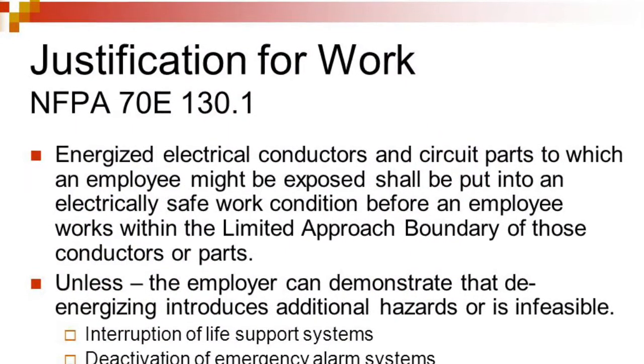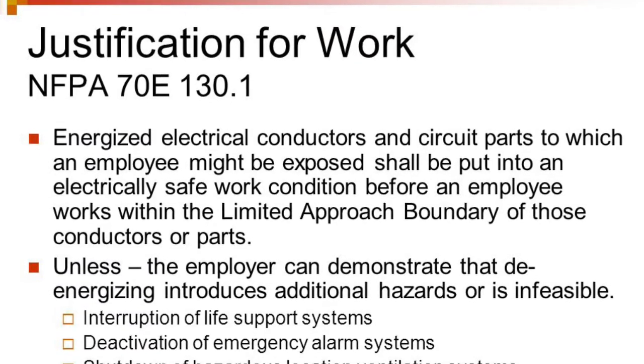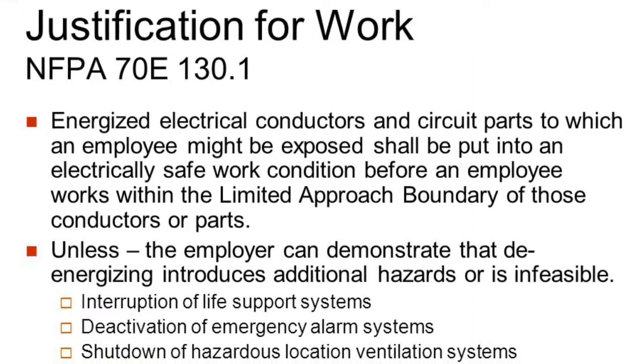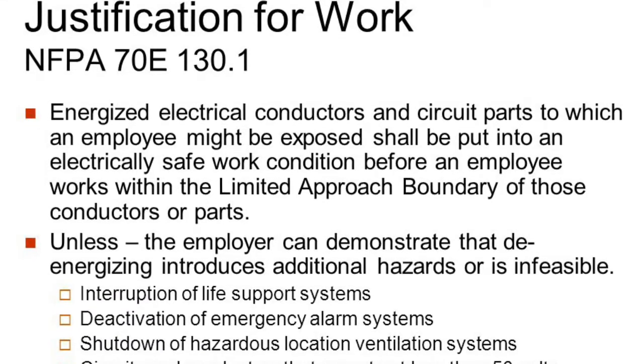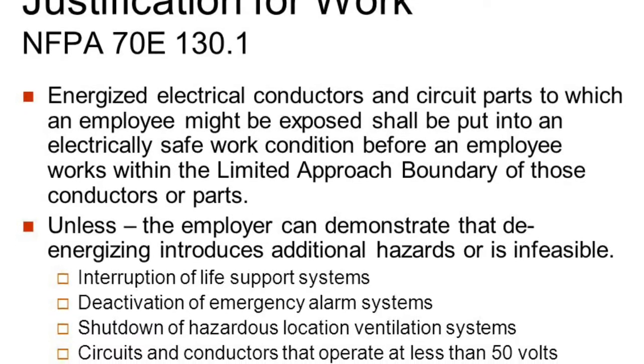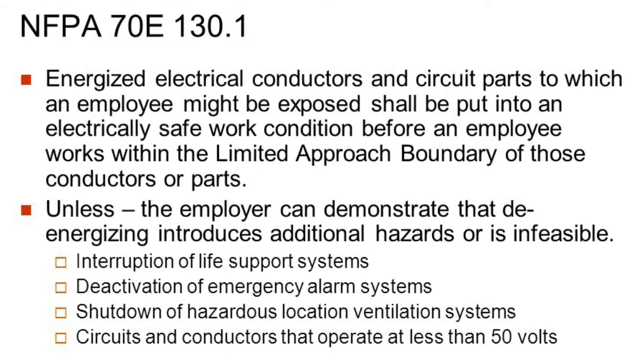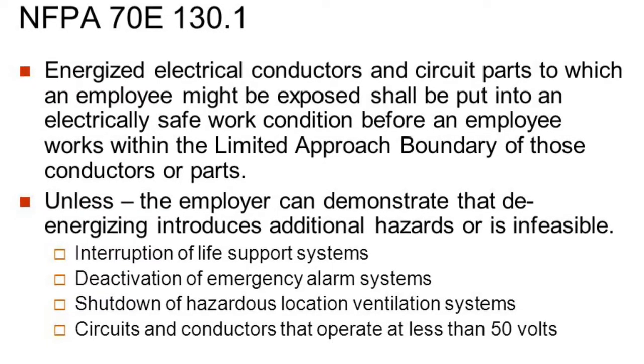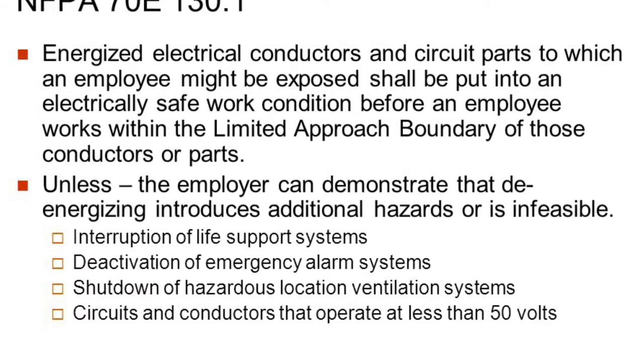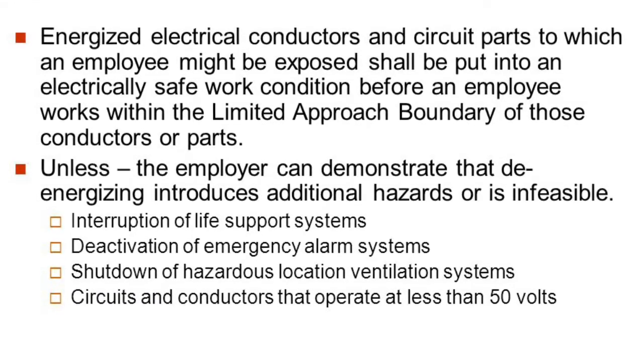Energized work shall be permitted where the employer can demonstrate that de-energizing introduces additional hazards or increased risk. Before authorizing energized work with the justification of a greater hazard, consideration should be given to the result of an incident that may occur — not only would equipment failure present the greater hazard, but the equipment could be inoperable for considerably longer than during a scheduled outage. For example, if life support equipment must be worked on while energized, there must be an alternative plan if an incident renders it inoperative. Another example is a hazardous area ventilation system that depends on electrical power, but where temporary ventilation may be available.